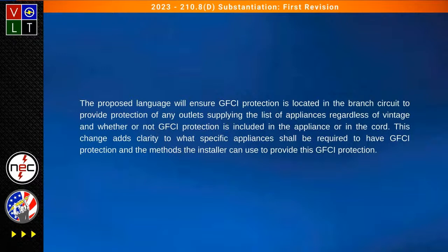So now in 210.8D, this is the first revision by Code Making Panel 2, what they stated here. They say the proposed language will ensure GFCI protection is located in the branch circuit to provide protection to any outlet supplying the listed appliances, regardless of vintage and whether or not GFCI protection is included in the appliance or in the cord. Then it says this change adds clarity to what specific appliances shall be required to have GFCI protection and the methods installers can use to provide this GFCI protection.